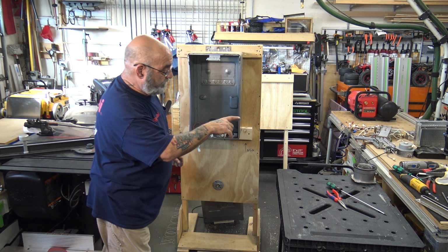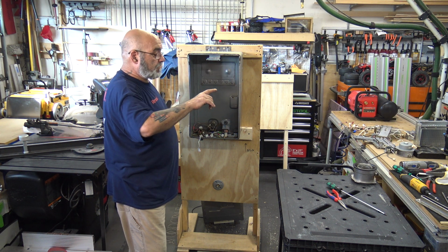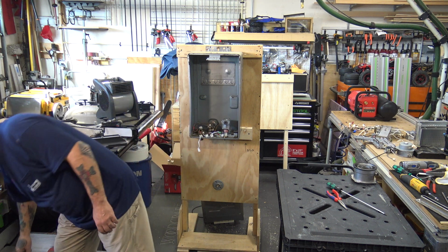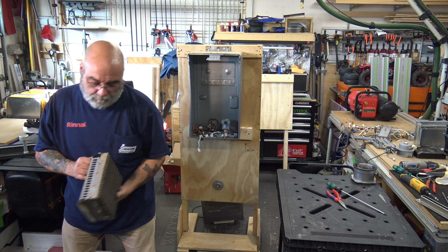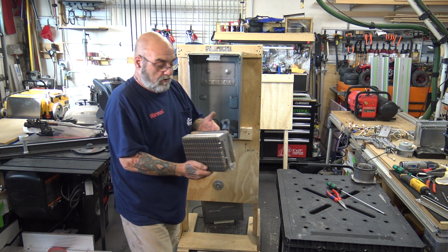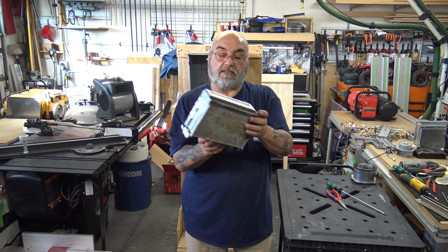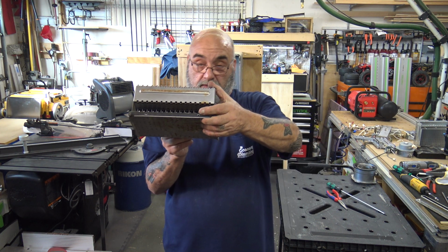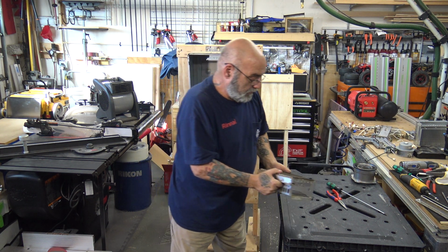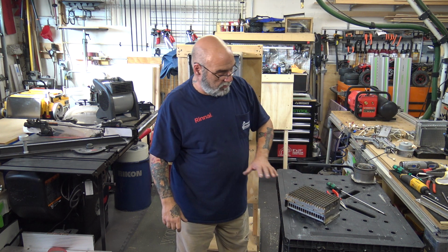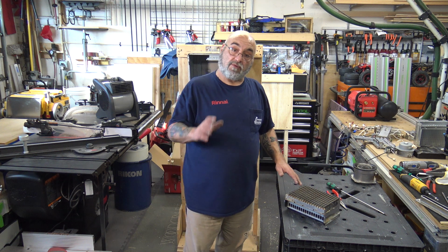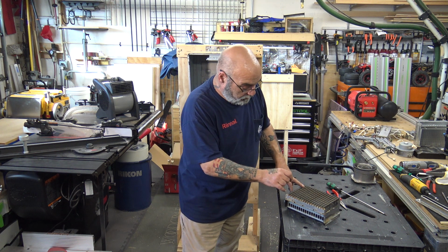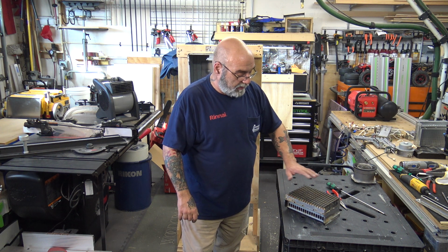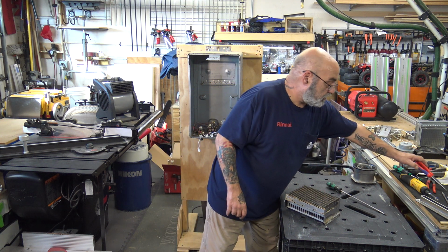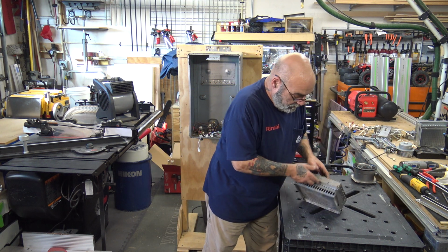Yes, I would blow out the fan, vacuum it, the burner. If we're going to reuse this burner, now you see there's a gasket on it. You're going to be putting a new gasket. You're going to blow this out with about 100 psi of air, so of course you're going to need your compressor. Blow it out. If you have a soft plastic bristle brush, hit it with a soft plastic bristle brush.